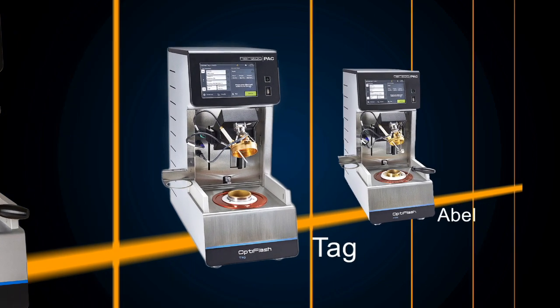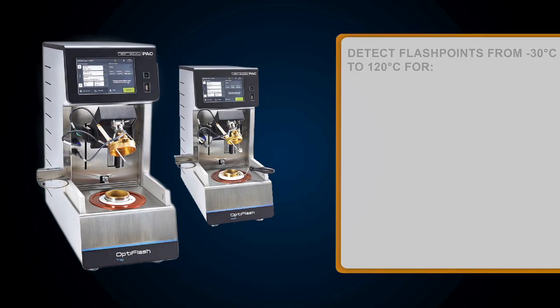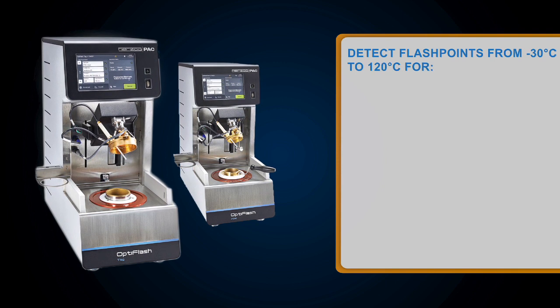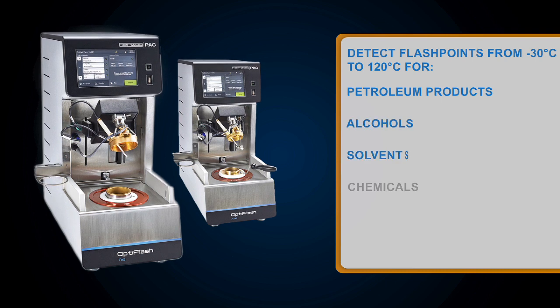The OptiFlash TAG and OptiFlash Abel models accurately detect flashpoints from minus 30 to 120 degrees Celsius for petroleum products, alcohols, solvents, and chemicals.